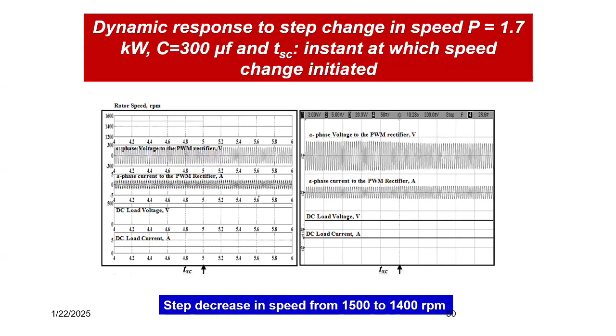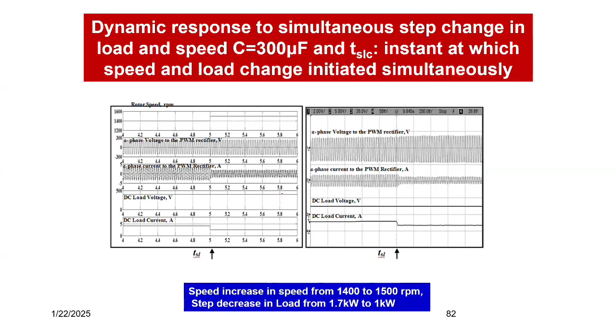Similarly, variable speed operation was carried out, like 1500 to 1400 RPM, 1400 to 1500 RPM, and so on. One reviewer for this work asked us to evaluate simultaneous changes in speed and load, like 1400 to 1500 RPM, 1.7 kilowatt to 1 kilowatt, to check whether the DC voltage remains constant, sinusoidal current shaping is maintained, and unity power factor is achieved.